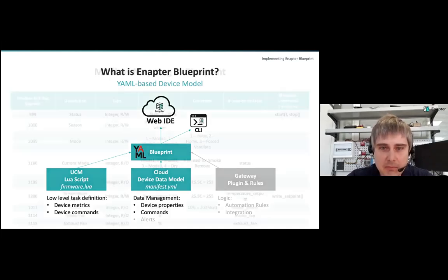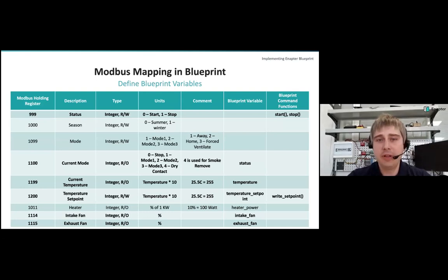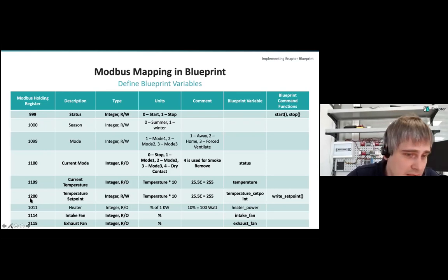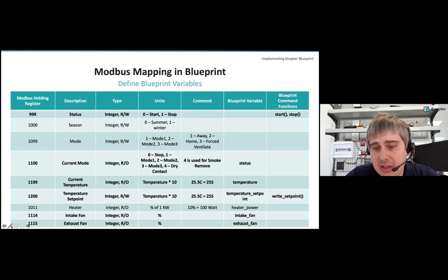Before we start, let's overview the Modbus register table again, but this time extended, because I've prepared mappings between the registers, the functions in our blueprint, and the variables. For example, Modbus register 999 will be mapped to the functions start and stop, whose role is to set either 1 or 0 into holding register 999. Register 1200, the temperature set point, will be mapped with a variable temperature set point in our telemetry.